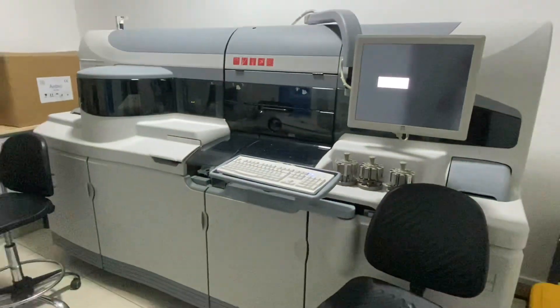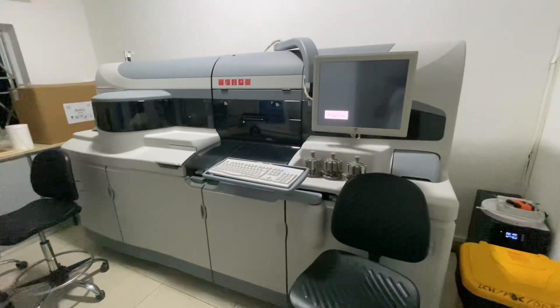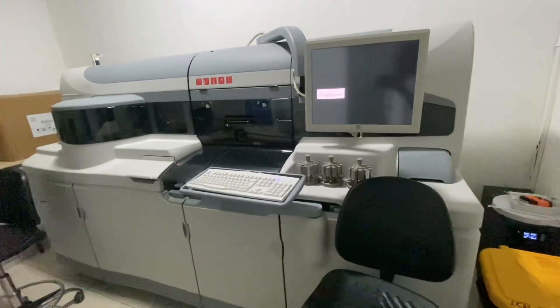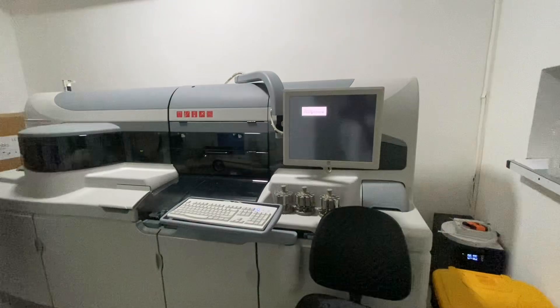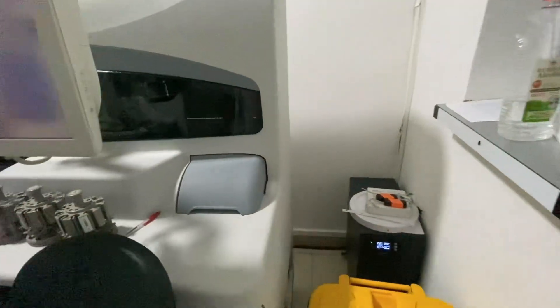It also has the ISE module installed, which means you can do your electrolytes on the same machine. That's a lot for one machine to do, so it's usually referred to as the workhorse of the lab — because it's going to do a lot for you at the same time. It's called the VITROS 5600 Integrated System because of what it can do simultaneously.